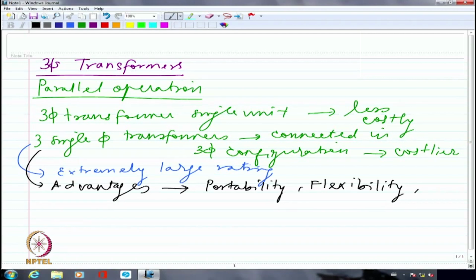To save a complete three phase unit, it will be definitely more expensive. But on the other hand, if I actually store even a couple of single phase units, it will be less expensive and I would be able to replace whatever is the phase that has conked out with one particular single phase unit. So obviously, storage as a backup is also simpler when I am looking at single phase units.